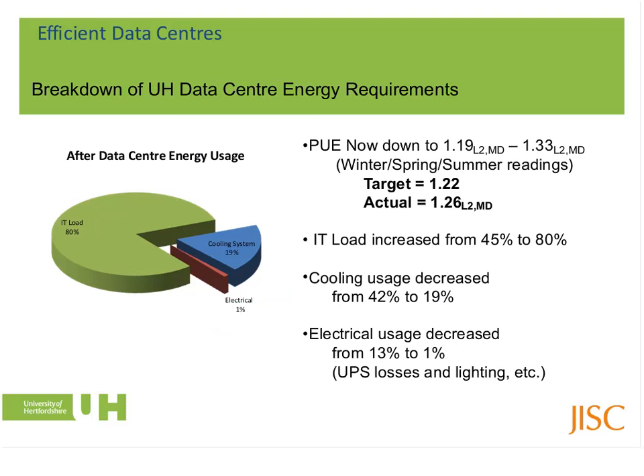So this is the result after the project. We got the PUE down to, well, actually it's even better than that in recent readings, but that's because we put a lot more IT load into the data center. After a year of running it operationally, we managed to get an annualized figure across the year of 1.26. Our target's 1.22, but I feel we're actually beating that now.